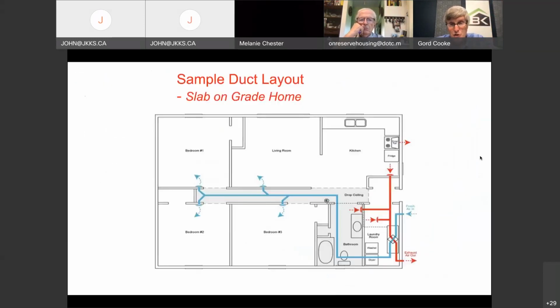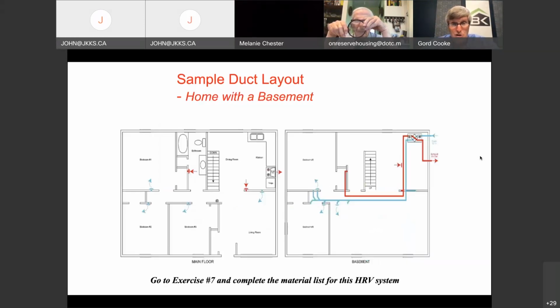A very nice solution. And we actually did this in a First Nations community that happened to be slab on grade, and they simply created in retrofit a drop ceiling in the hallway and they installed the HRV in the laundry closet, bottom right. They exhausted from the kitchens and the bathroom. They created a drop ceiling in the hallway that allowed them to put fresh air into the living room and to the bedrooms. Fairly simple, straightforward retrofit in this application. They had to drop the ceiling about 8 inches in order to get that done. And you might say, well, that's too low. Well, fair enough. If you have a basement, of course, you could install the equipment on the right-hand side there in the basement and simply run into the floor cavities to get you there.